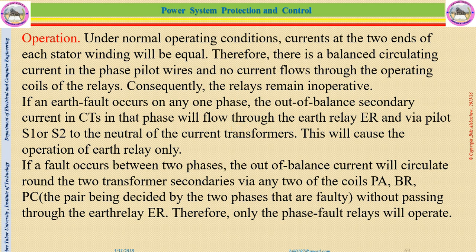So if the fault occurs between two phases, that means the out of balance current will circulate around the two transformer secondaries via any two of the coils PA, PB or PC. Their pairing is decided by the two phases.